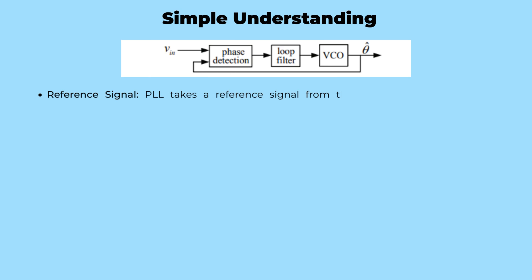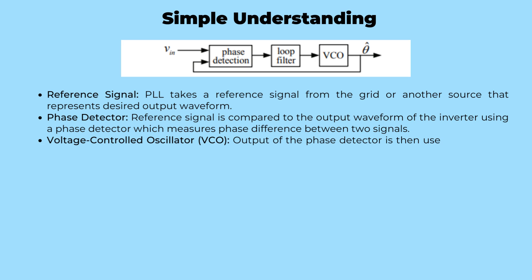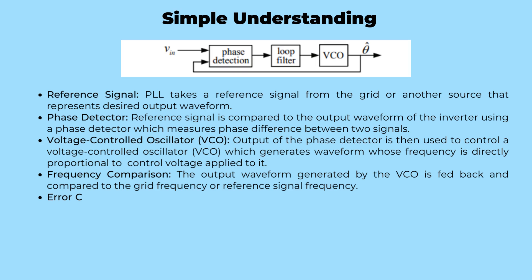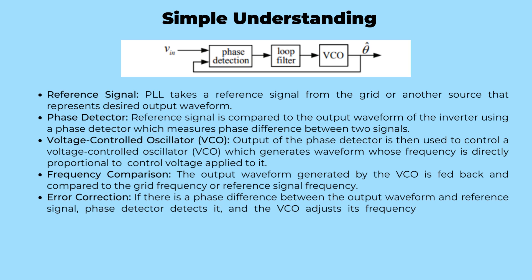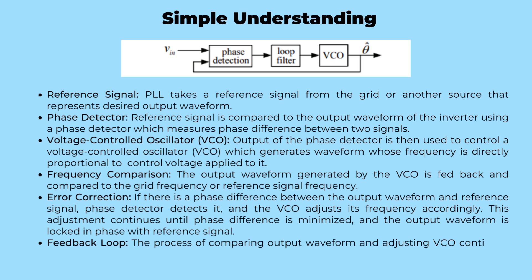The PLL takes a reference signal, which could come from the grid or another source representing the desired output waveform. This reference signal is then compared to the output waveform of the inverter using a phase detector, which measures the phase difference between the two signals. The output of the phase detector is used to control a voltage-controlled oscillator, which generates a waveform with a frequency directly proportional to the control voltage applied to it. The generated waveform is fed back and compared to the grid frequency or the reference signal. If a phase difference is detected, the voltage-controlled oscillator adjusts its frequency accordingly, and this iterative process continues until the phase difference is minimized, locking the output waveform in phase with the reference signal.